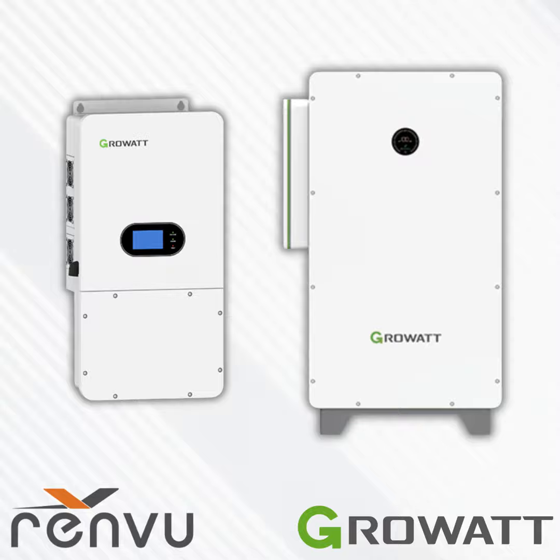Just like the SPH, we tried to remove all the extra components that you need. So in this solution, we have the ATS, all the controls, and we have internal MPPTs connected directly into the inverter. The connections are made with MC4 standard connectors, and you have up to 2 strings connection on each MPPT. Each WIT size has a different number of MPPTs. So for example, the 100 kilowatt has 10 separate MPPTs, just to try to get it a little bit more optimized.